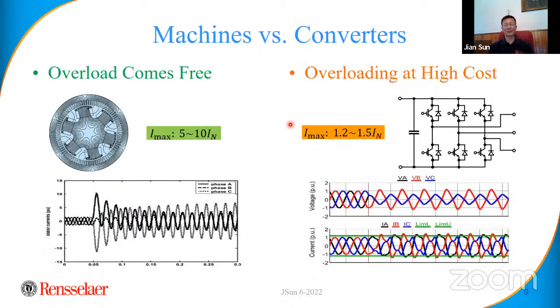The second one has to do with the physical aspect of the machine. In machines, it's basically copper and iron, and then insulators, right? So if you have a fault, and faults are everywhere in the power system, if you have a short circuit really close to the generator, the generator is going to drive a huge amount of fault current, 5 times, even 8 times. You cannot do anything about it, right? It takes time to clear the fault. So during the fault, the generator will feed current into the fault. And we rely on that to design all the protection and the rest of the system, right? It comes with the generator. So the overloading capability comes free, and we design the whole system based upon that.